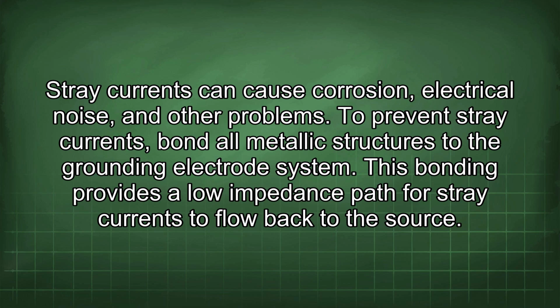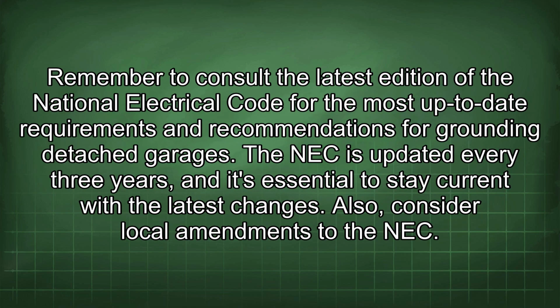To prevent stray currents, bond all metallic structures to the grounding electrode system. This bonding provides a low impedance path for stray currents to flow back to the source. Remember to consult the latest edition of the National Electrical Code for the most up-to-date requirements and recommendations for grounding detached garages. The NEC is updated every 3 years, and it's essential to stay current with the latest changes.